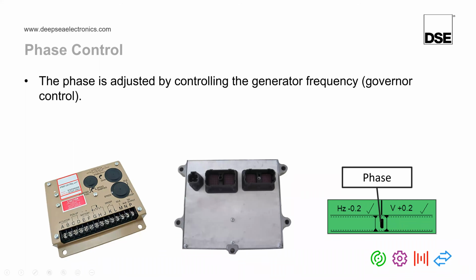And under these grommets, which are used for IP isolation, so stop water ingress, there will be some additional on-circuit potentiometers, which, as you can see here, set the nominal speed or nominal frequency of the generator. So normally what you would do with the DeepSea module disconnected, you would adjust the onboard potentiometers to make the governor run the generator at nominal frequency, and also adjust on the AVR its same potentiometer for nominal voltage. I hope that answers the question.